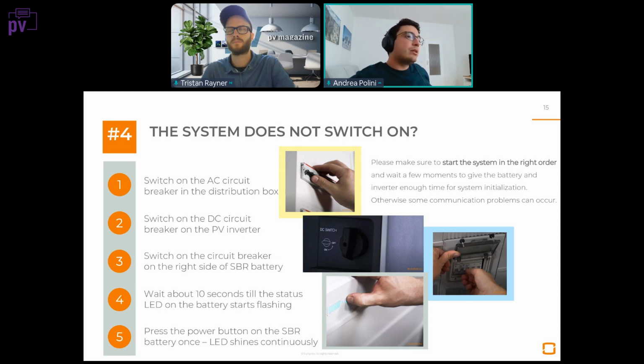And so if this turn-on procedure does not work, then I would recommend doing the opposite procedure. Shut down everything first. So turn off the DC and the AC. Wait a few minutes until everything is shut down and the capacitors inside the inverter are totally discharged. Then first turn on the battery. Then wait 5 minutes. Then turn on the PV DC breaker, and then finally turn on the AC box.